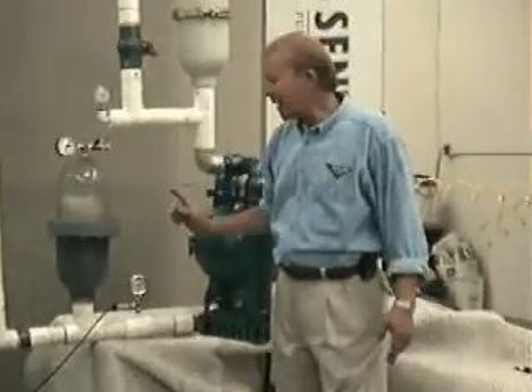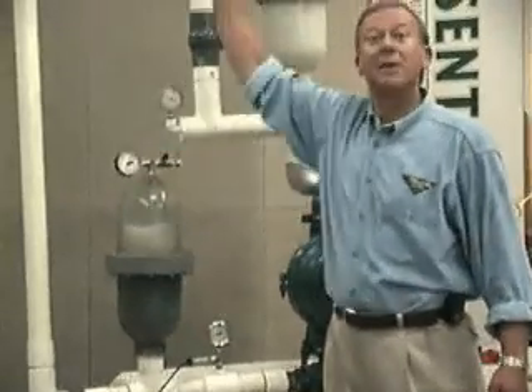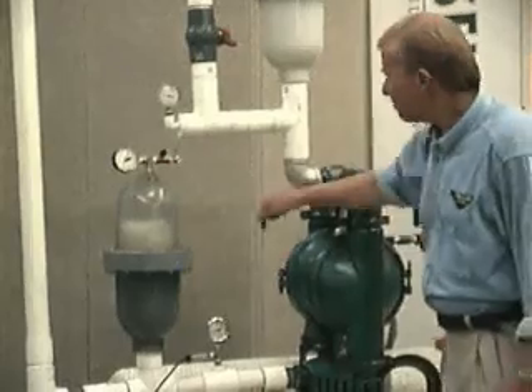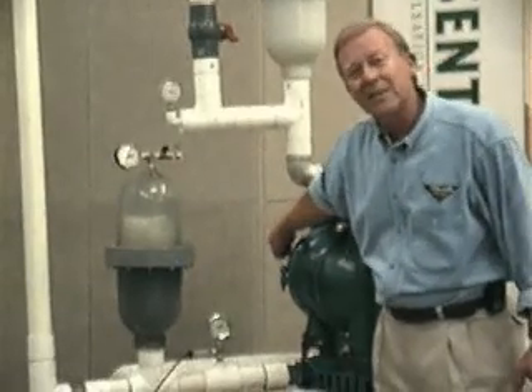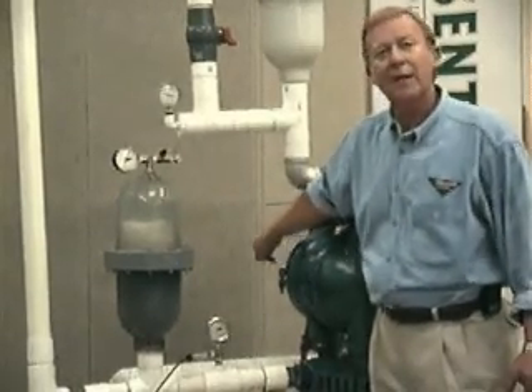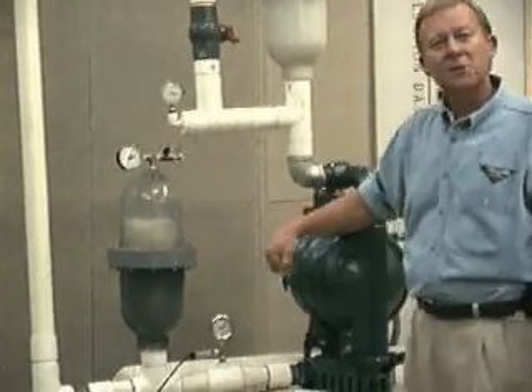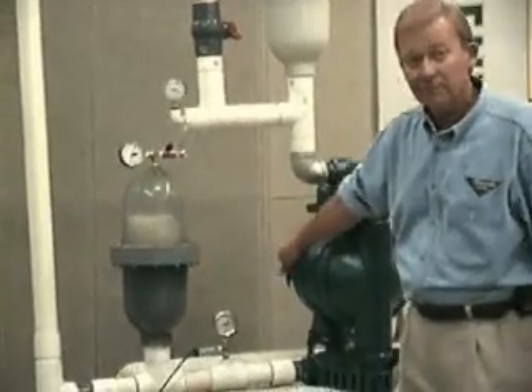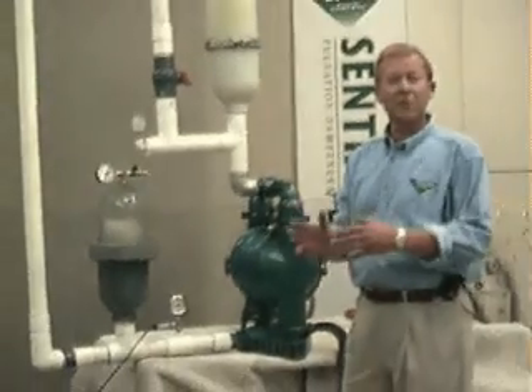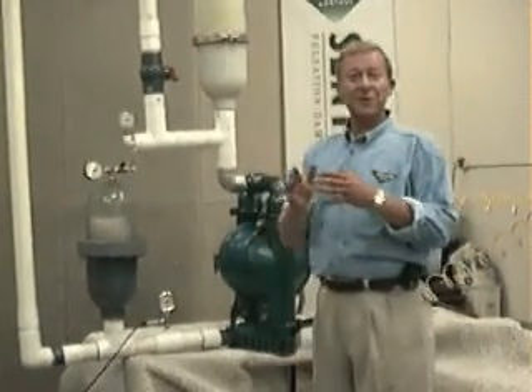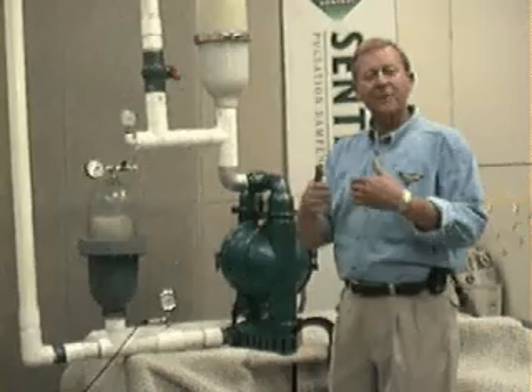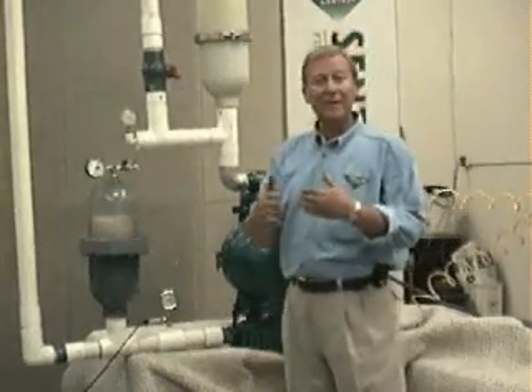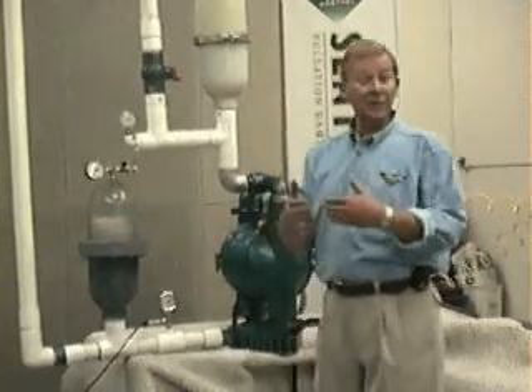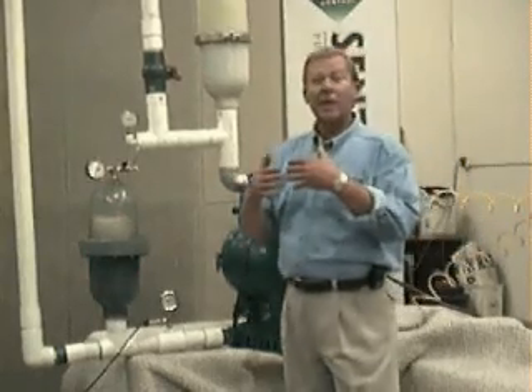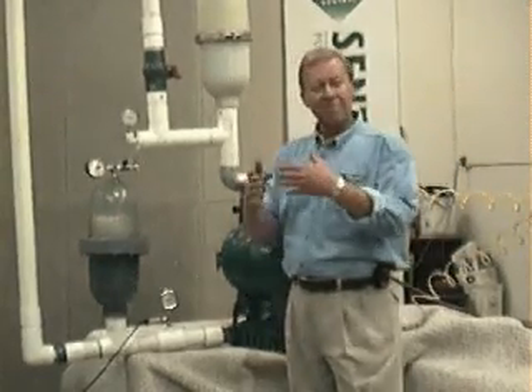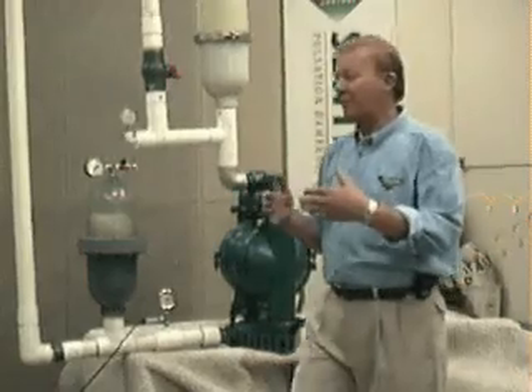The pressure spike can't go back up the discharge line because of the positive head. But the other side of the pump is opening its inlet valve ball to accept liquid. It's a low pressure area. The spike rushes over there, slams into the diaphragm and distorts it. With a rubber diaphragm, it stretches it, tends to separate it from its fabric, causing it to weaken and tear and fail. With a Teflon diaphragm, it starts to cold flow with this unbalanced pressure, stretches and fails.